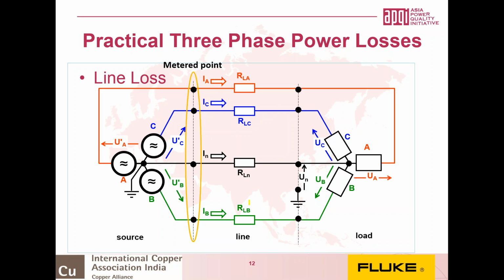So according to the IEC publication Efficient Electrical Energy Transmission and Distribution, the overall loss between the power plant and user can be easily between 8 and 15%. Overhead lines account for about 2.5% of that loss, and then the transformers which step down the voltage account for between 3 and 5%. On average, the losses are double those between the substation and the user. So the publication mentions three causes of these losses. First is the Joule effect, where energy is lost as heat in the conductors, or there's magnetic loss where energy is placed into a magnetic field, and then there's a dielectric effect where the energy is absorbed by the insulating material. Here we'll focus on the line losses, and particularly the line losses at the user side of the system.